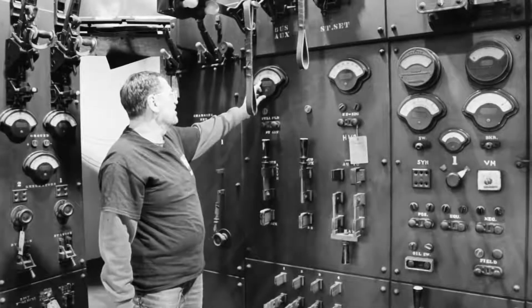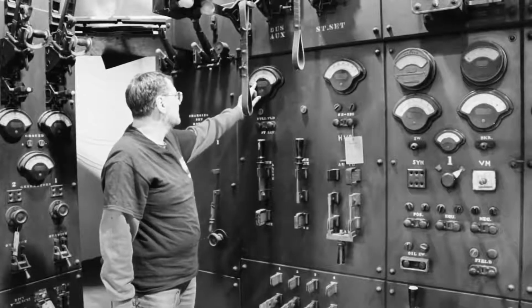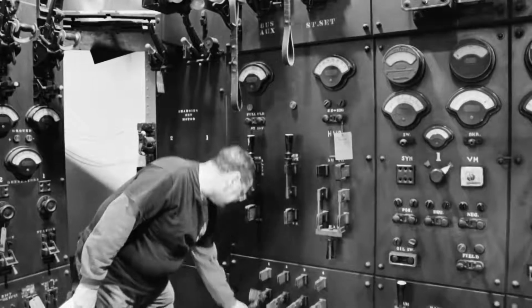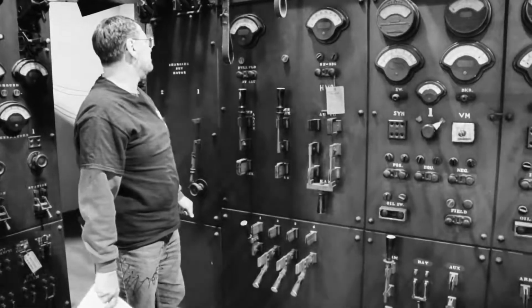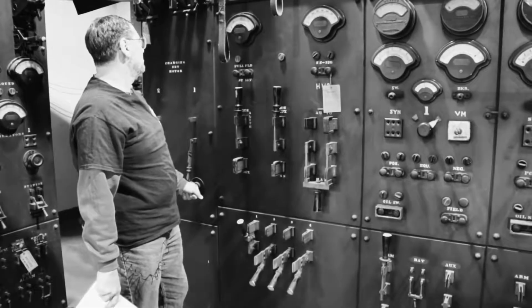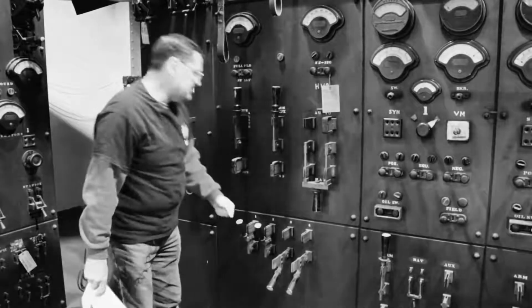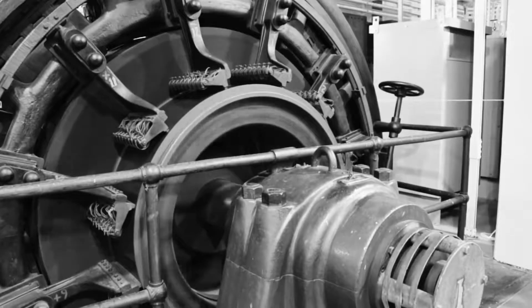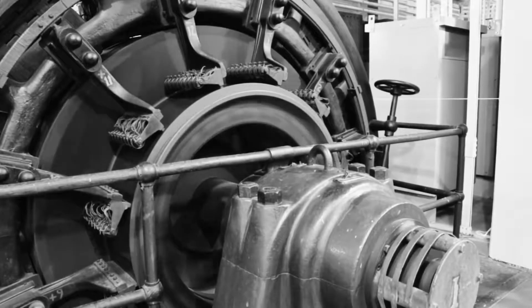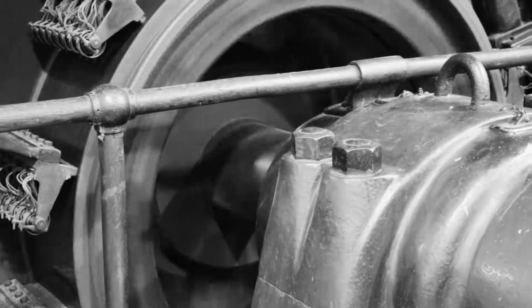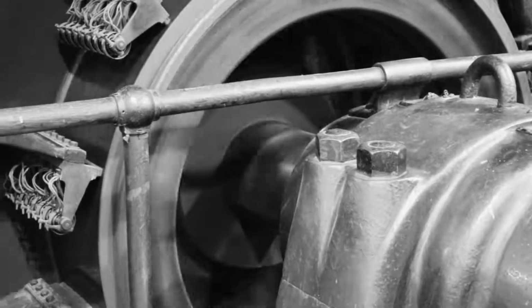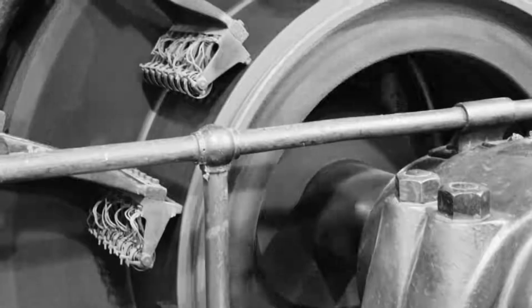The DC current is slowing down. And one by one I'm going to cut out the starting resistors until it comes up to speed. Full speed on this machine is 250 RPM. Right now, the rotary converter is running directly off the third rail as a direct current motor.